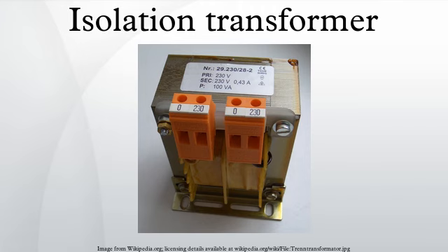This can be avoided by using an isolation transformer with the primary and case connected to shore earth, and the secondary floating. A metal safety screen between primary and secondary is connected to shore earth. In the event of a fault current in the primary, it will cause the fault current to return and trip a shore-based circuit breaker rather than making the hull live.